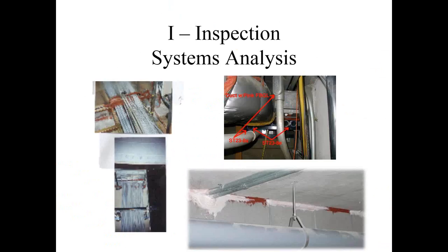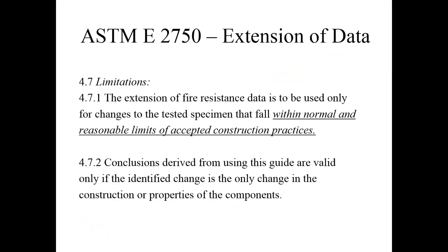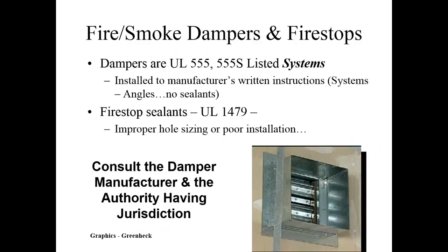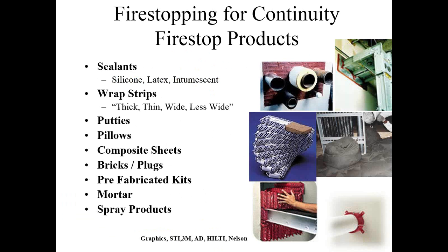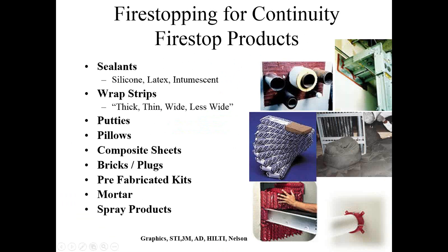I know I've got a picture of a foam block in here, and the foam blocks are installed in a certain direction. They're installed a certain number of them. Here it is right here. So if we take this picture, in this case the blocks completely fill the assembly. The blocks are flush with the wall, so they're in the 4-inch direction instead of the lengthwise direction. And then the system would explain whether to put sealant around it.